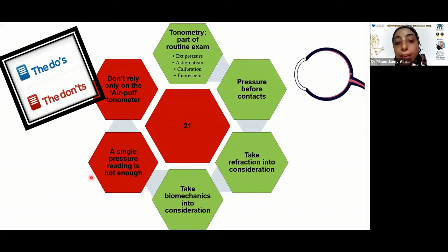The calibration should be checked once or even twice per year. Other things include off-axis applanation, blepharospasm and differential IOP. Some pitfalls during IOP practice, as I mentioned: tonometry is part of the routine examination, pressure before contact, take refraction into consideration, as well as biomechanics. Never treat a patient just because he has a pressure of 21 or more. Do not rely on the air puff. A single pressure reading is not enough.